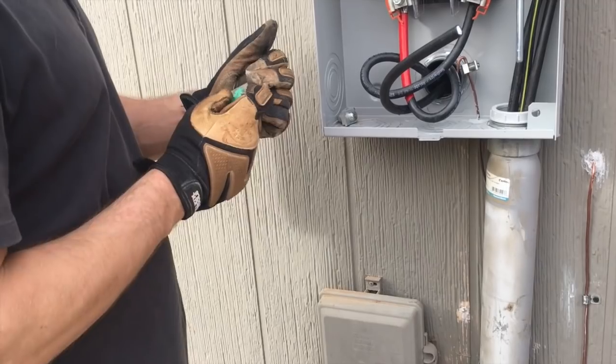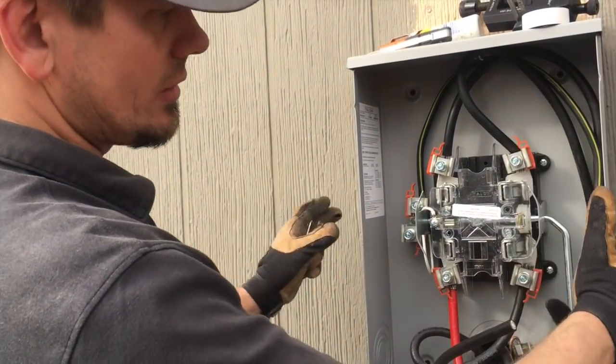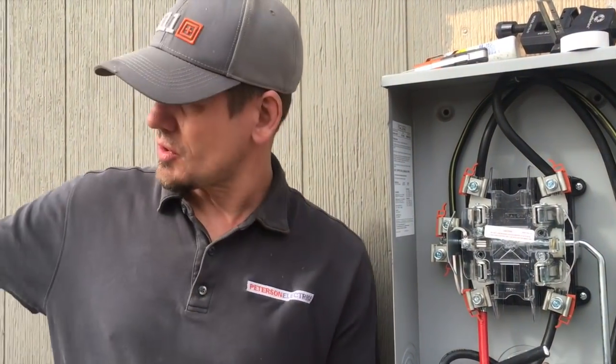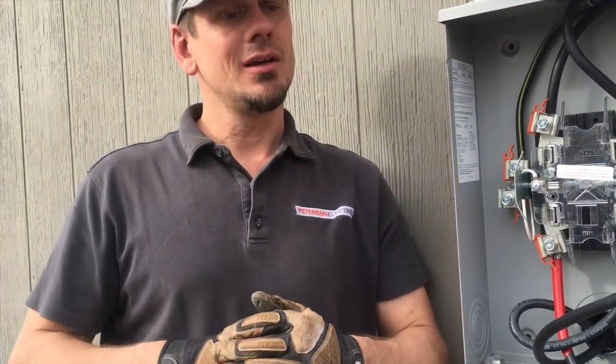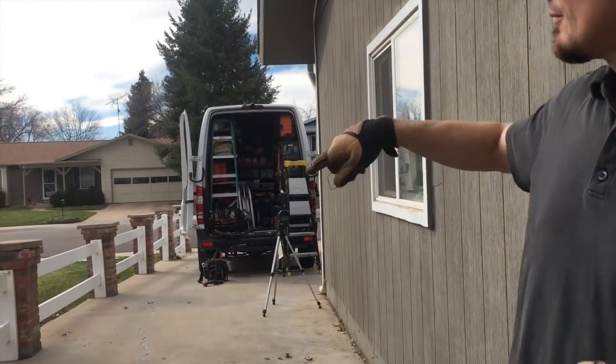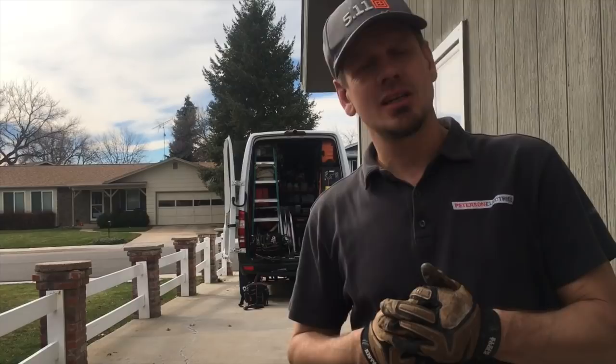Fort Collins won't let me cut the tag on the can, so they came out within about an hour and opened it up. The max they can go up to is 150 amps on this two-aught aluminum. To re-pull it as four-aught is about $1,400 since it was already bored. If it hadn't been bored, a quote from another utility for boring was about $4,000 — due to a sidewalk, tree, or neighbor issue. So boring alone can be $4,000, plus the $1,000 upgrade fee, plus any disconnect/reconnect fee.